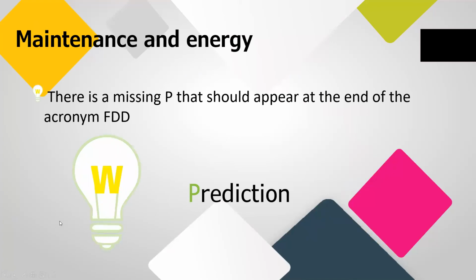However, we talked about fault detection and diagnostic, FDD. There is a missing P that should appear at the end of the acronym FDD. That P stands for prediction. Nowadays, maintenance practices in the field of facility maintenance are mainly based on corrective maintenance. So late actions are taken following a user complaint or an unplanned failure. The lack of budget and human resources, as we just discussed, limits the use of preventive maintenance to the minimum level of mandatory inspection and critical installation.